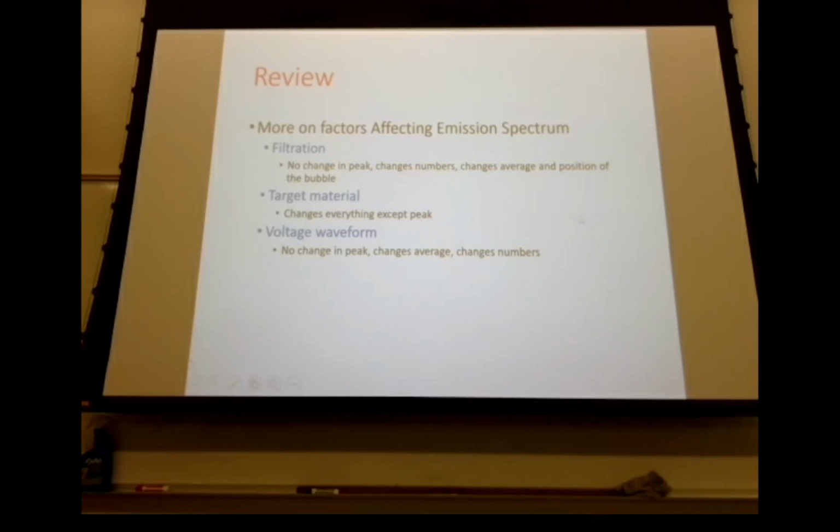One thing we didn't talk about is target material. If you remember back to whichever chapter this was in, target material changes everything. You're never going to change target material. The only time that you're going to see a change in target material is if you happen to cross-train into mammography. They use totally different targets. So in diagnostic radiology, it doesn't do anything. If we shot a hand on a mammo machine, it would be a totally different set of techniques.